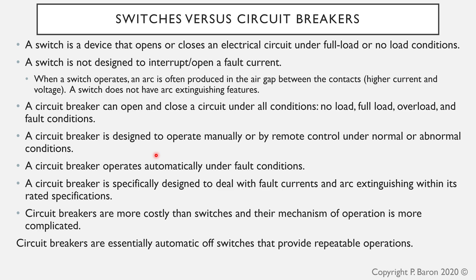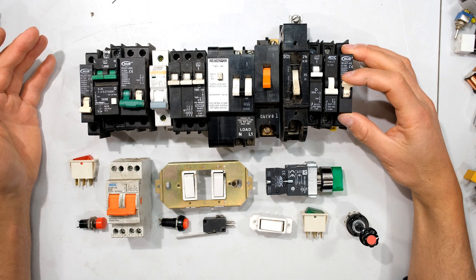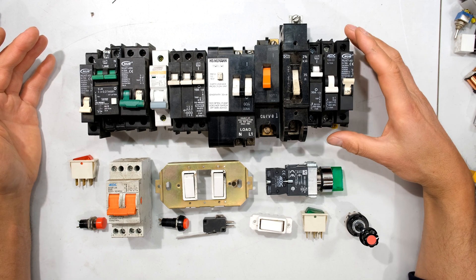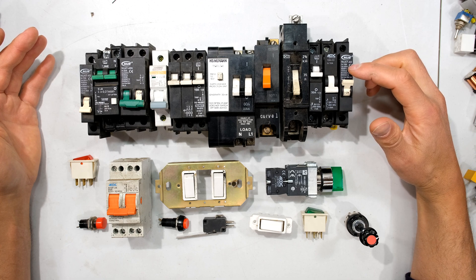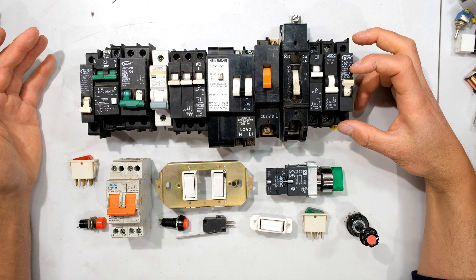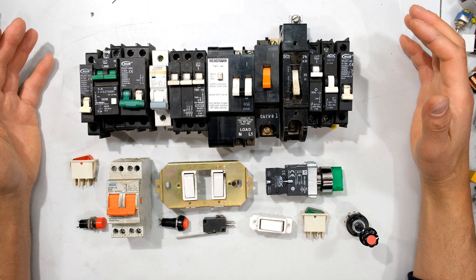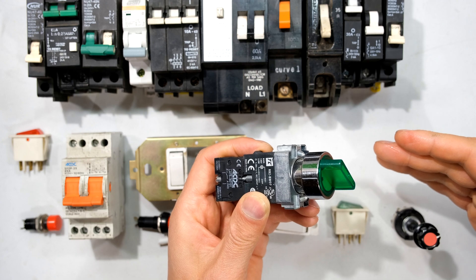A circuit breaker operates automatically under fault conditions. You can manually operate the circuit breaker — closing it and opening it — but when connected to a circuit and the current exceeds the rated current, in this case it says 16 amps on the front, if it exceeds about 16 amps this will automatically trip.